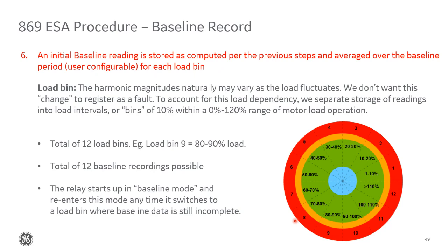The idea is that certain characteristics are load dependent, so you'd probably inherently see different frequency magnitudes as you go up in load. And we don't want to falsely think that this change registers as a fault, when it's actually not. So every time the motor significantly changes in load, we record another baseline register for that specific load bin. So we have 12 different load bins in total, and we could potentially have 12 different groups of baseline recordings.